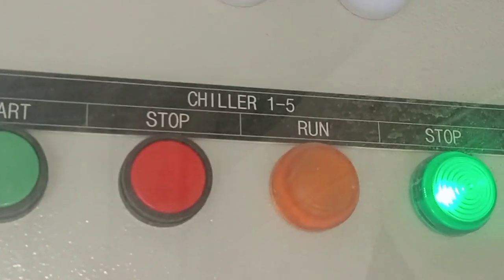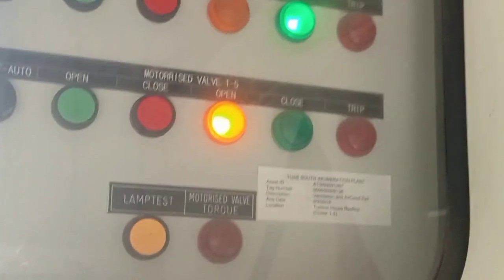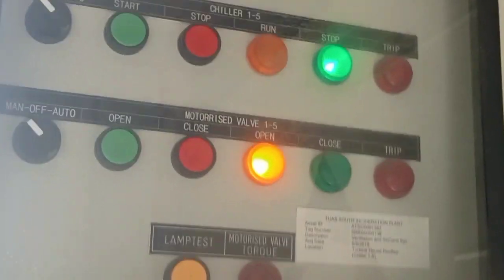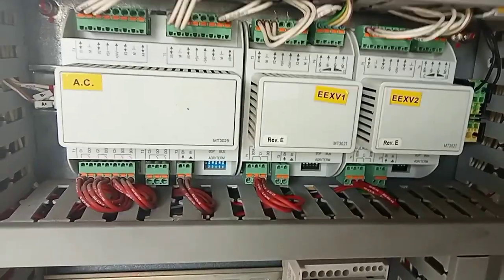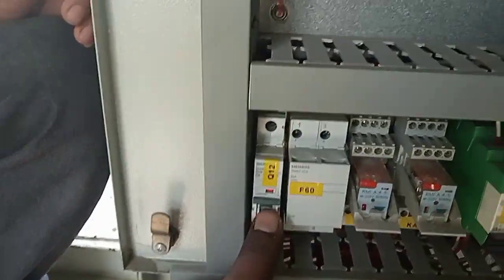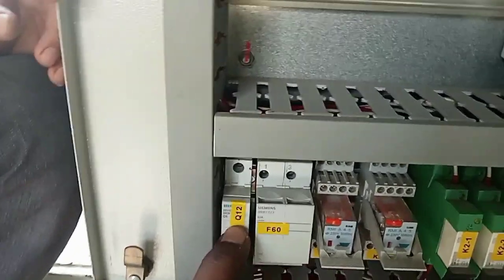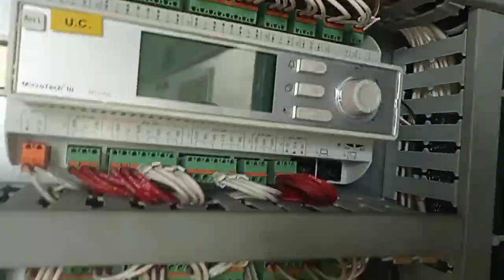So we'll replace these two after we test run the unit. This chiller 1-5 cannot run because of these two modular problems. So we just turn off the main MCB. Just off the MCB, see, now there's totally no power.